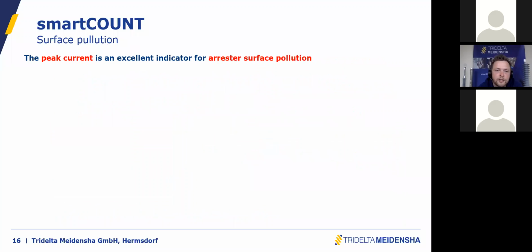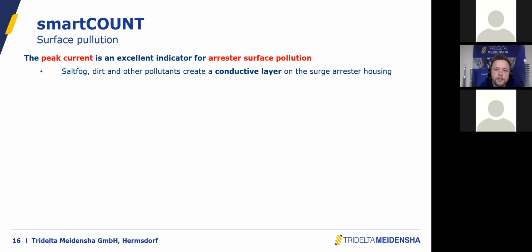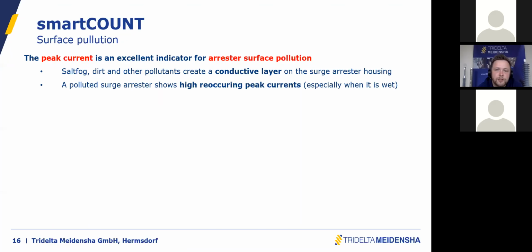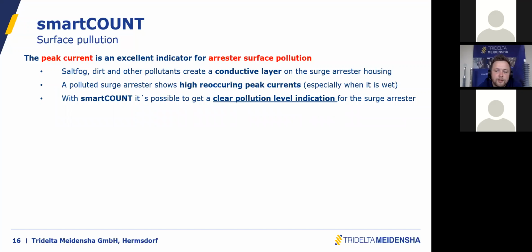And the third case, surface pollution, is somehow similar, but the difference is that if the surface of the surge arrestor is polluted and wet, it of course has something to do with the weather and with the surroundings of the surge arrestor, and there might also be the possibility that the surface dries off or cleans afterwards after rain. So you will see the weather influencing this behavior. It's just the same as with humidity ingress. You have a conductive layer, you have high peak currents, and therefore we show how we measure it with the smartCOUNT.